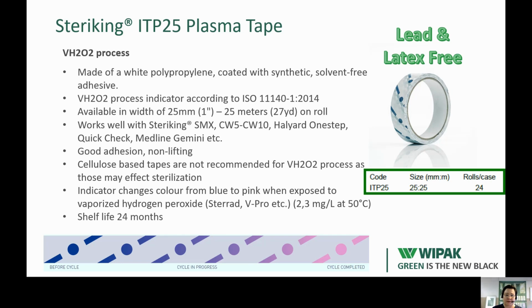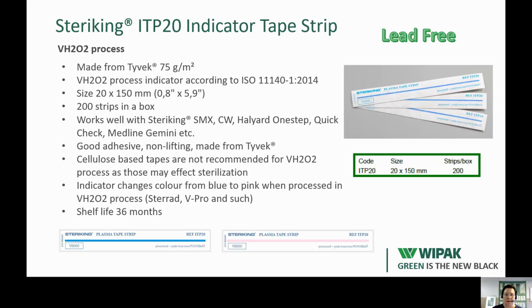And then there is a certain gas concentration of hydrogen peroxide where the color change is going to happen. So it's 2.3 milligrams per liter at 50 Celsius degrees when the color change is happening. And then the shelf life of this tape is 24 months. We also have this indicator tape strip for plasma sterilization. This we have had in our range for a very long time already. The tape in reel format is a bit newer product.